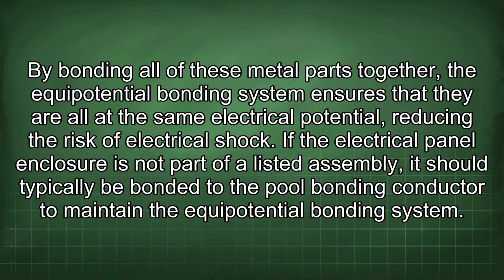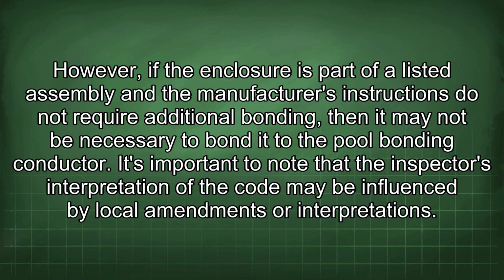If the electrical panel enclosure is not part of a listed assembly, it should typically be bonded to the pool bonding conductor to maintain the equipotential bonding system. However, if the enclosure is part of a listed assembly and the manufacturer's instructions do not require additional bonding, then it may not be necessary to bond it to the pool bonding conductor.